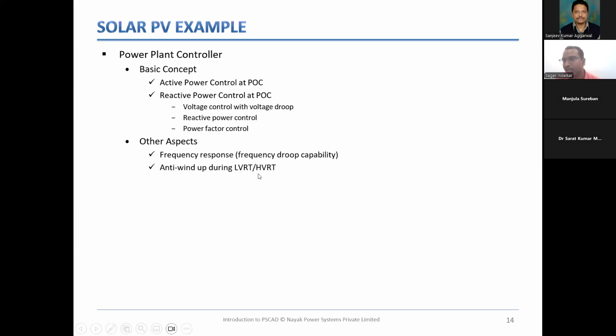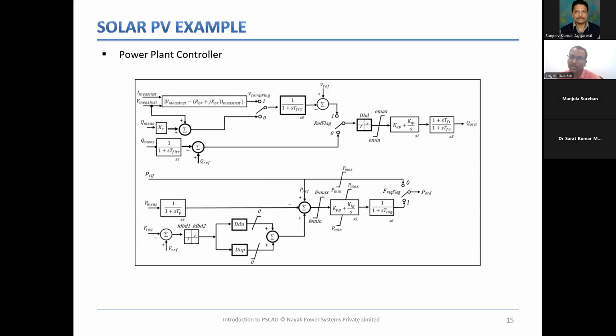The reason is simple. LVRT, HVRT are very transient events, so they change very quickly. But the PPC is a slow device, so we find it very difficult for it to respond to fast changing voltages. So it typically takes a decision not to respond to the transient. That decision is basically to freeze the P and Q output to whatever it was before that event. So the PPC freezes, and it will let the inverter take control to keep the plant running and operating, even during a low voltage or high voltage ride through event. The PPC basically has control loops, active power and reactive power control loops, that will generate your P and Q order.